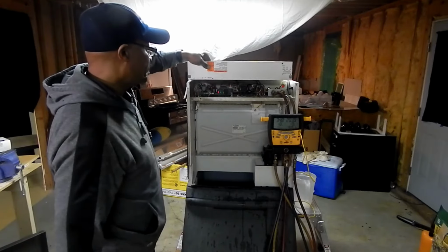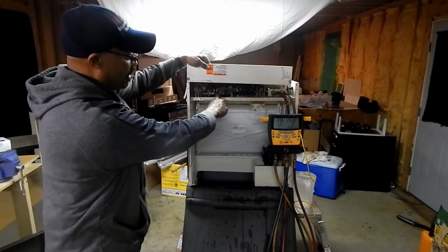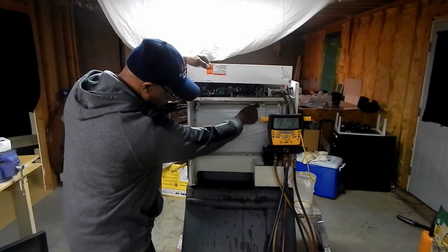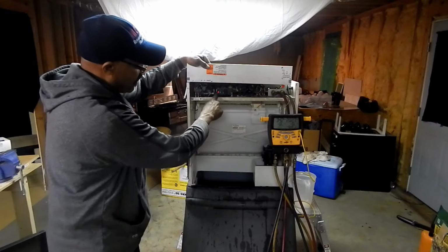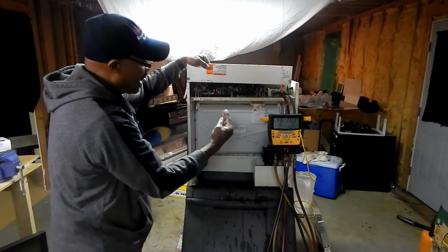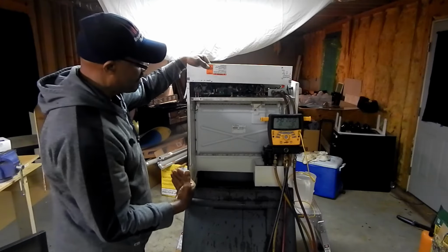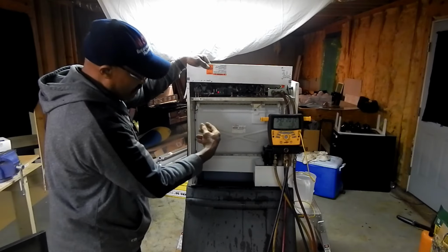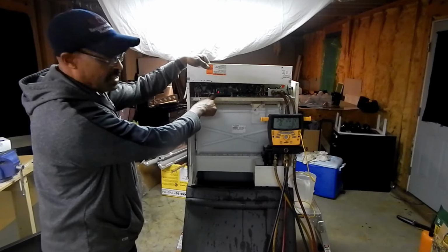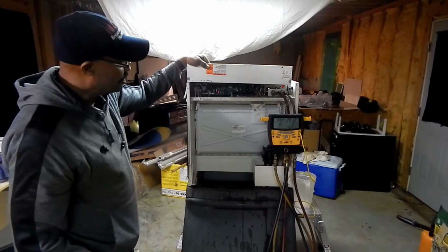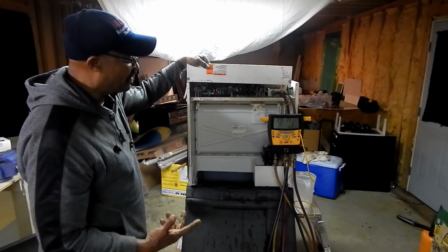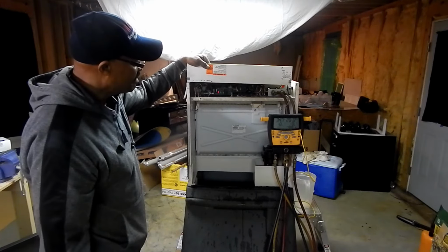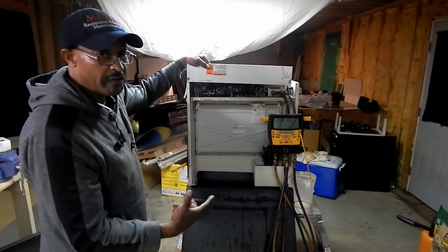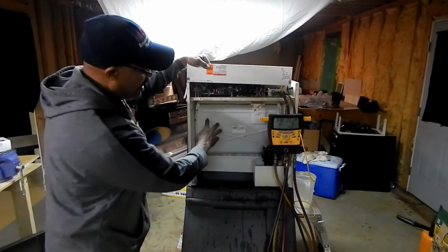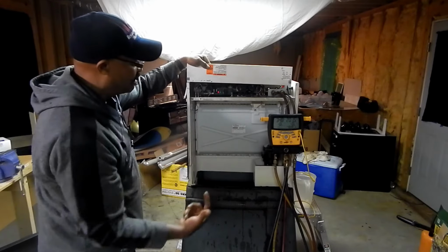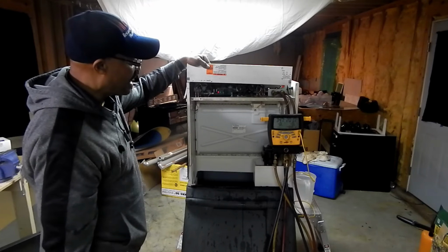We're back on. Seeing that this red light is starting to blink. That means that water is touching that ice thickness probe. So now when this becomes solid, after like 30 seconds, it's going to go into harvest. As long as it's blinking, water's going to keep coming over, but we're starting to get a solid red light right now. So once it stays solid, it's about 30 seconds, I believe, 15 to 30 seconds. It's going to put the machine in a harvest mode. It's going to bring hot gas behind the plate. It's going to allow the ice to fall off. It's starting to get a solid light right now.